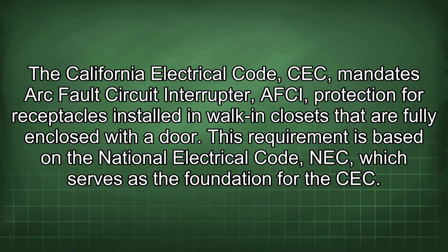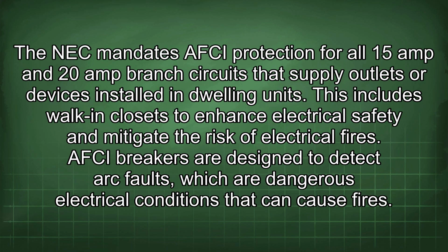California Electrical Code (CEC) mandates arc fault circuit interrupter (AFCI) protection for receptacles installed in walk-in closets that are fully enclosed with a door. This requirement is based on the National Electrical Code (NEC), which serves as the foundation for the CEC. The NEC mandates AFCI protection for all 15 amp and 20 amp branch circuits that supply outlets or devices installed in dwelling units. This includes walk-in closets to enhance electrical safety and mitigate the risk of electrical fires.